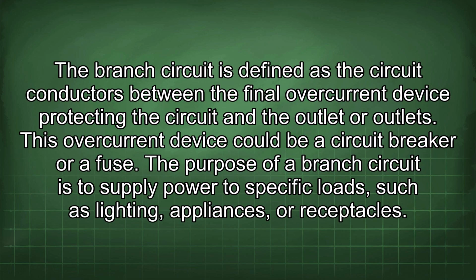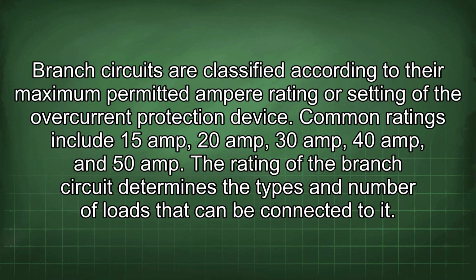The branch circuit is defined as the circuit conductors between the final overcurrent device protecting the circuit and the outlet or outlets. This overcurrent device could be a circuit breaker or a fuse. The purpose of a branch circuit is to supply power to specific loads, such as lighting, appliances, or receptacles. Branch circuits are classified according to their maximum permitted ampere rating or setting of the overcurrent protection device. Common ratings include 15 amp, 20 amp, 30 amp, 40 amp, and 50 amp. The rating of the branch circuit determines the types and number of loads that can be connected to it.